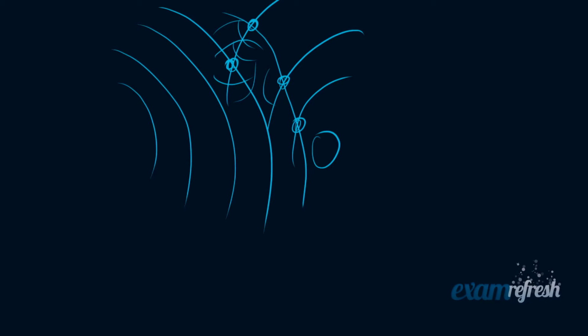Those will create more ripples that head off in all directions. Well, those little points are what we see as speckle in our machine, because the machine is receiving the sound, and it's taking a certain amount of time to receive it, so it thinks, oh, I must place a dot there. So the machine gets confused by these waves that it's receiving that it actually didn't send.